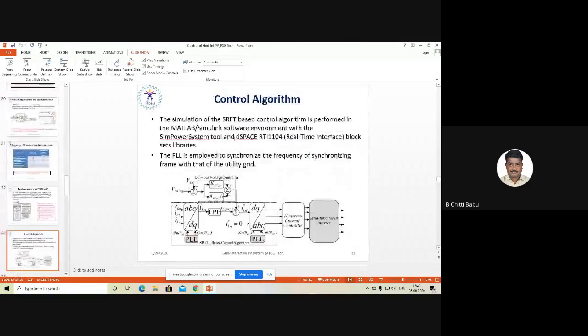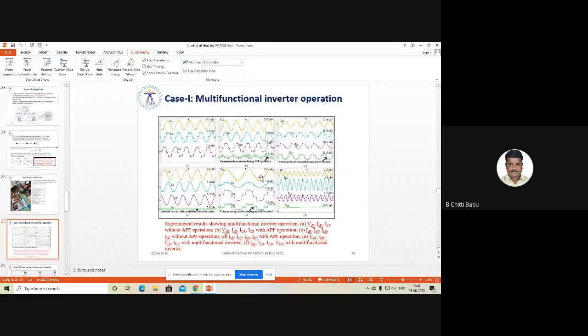You can see the figure very clearly. As you are using the fourth leg, whenever a non-linear load is connected, you see the neutral current is flowing, and moreover the neutral current has a certain value, about 20 amperes per division. It implies the neutral current magnitude is higher when non-linear or unbalanced loads are connected. So this has to be compensated. If not, the neutral current will cause overheating. It will overheat the neutral wire. So now this has to be compensated by the fourth leg, so that as it compensates the neutral current, the ISN becomes 0. So it means there is no third harmonic current injection here. Okay. That is what. Yeah.